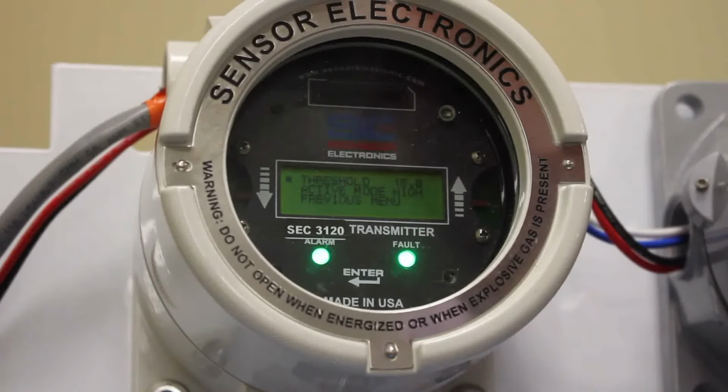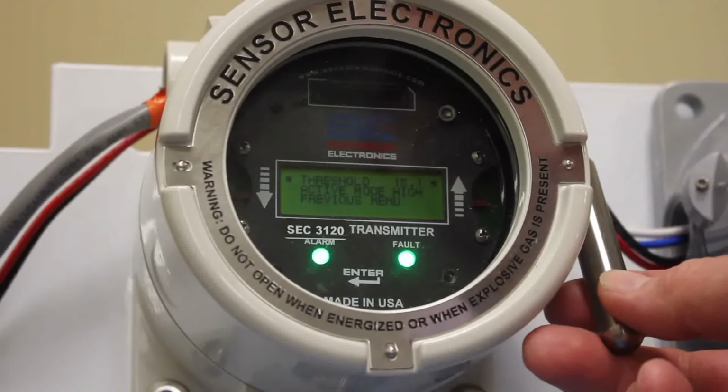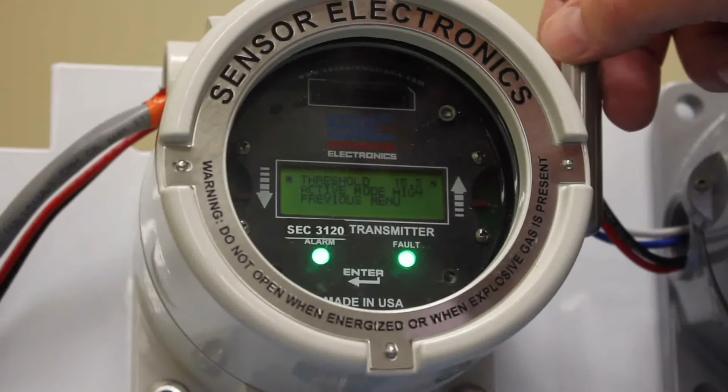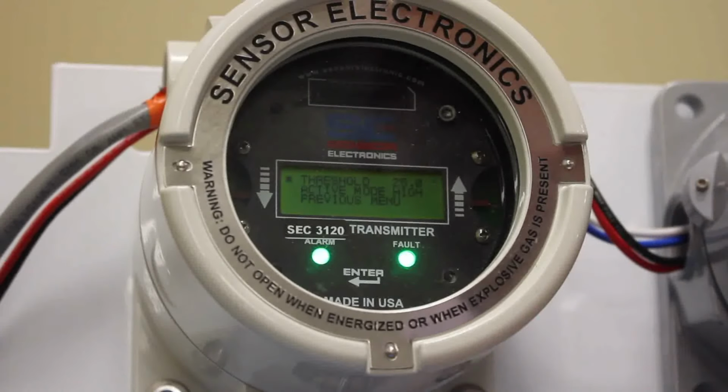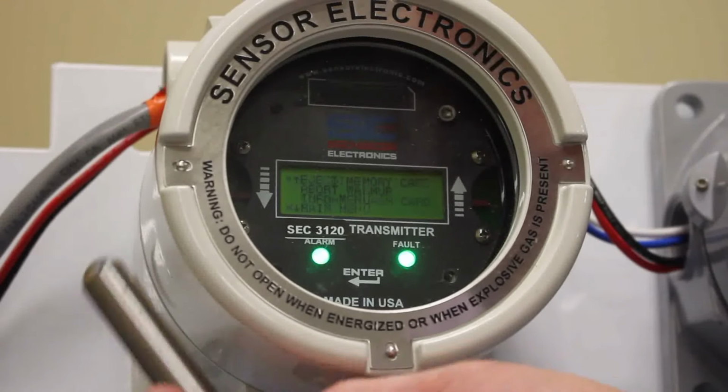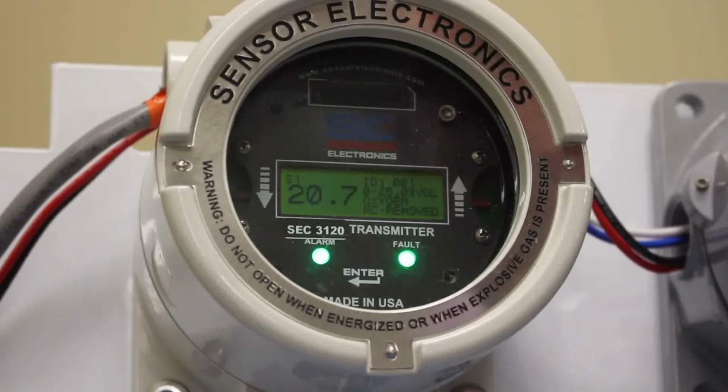Now we'll go to high, and the high threshold is a true high alarm. In the case of oxygen-enriched areas, it can become explosive. So we'll set the high alarm for 25% by volume, which is typically the full scale range of the oxygen sensor. So set for 25, that's active high, previous menu, select Enter, save changes. And with any luck, we should be in a non-alarm condition, and everything's good.